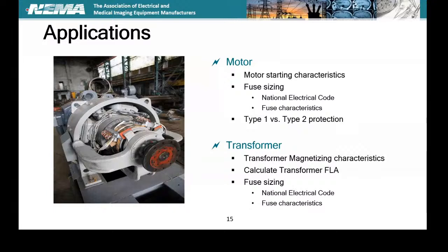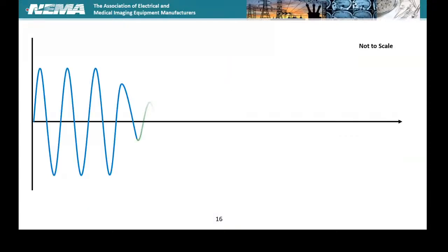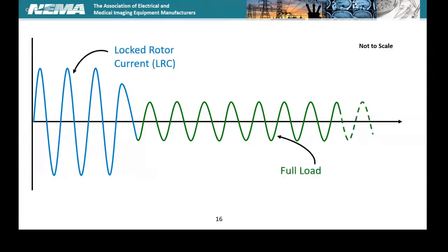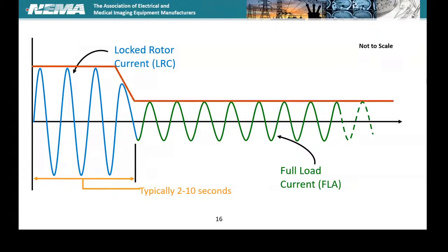The slide I have coming up here is blank until I hit the button. So this is the starting characteristic of the motor. You've got high locked rotor current when you first start it up. We have a time duration, and then we have a steady state full load current, full load amperes, from there on out after startup. This is the current curve for that motor. We have to look at what value this locked rotor current up here is compared to our full load ampere level down here, and typically you might see 6 times the full load current.